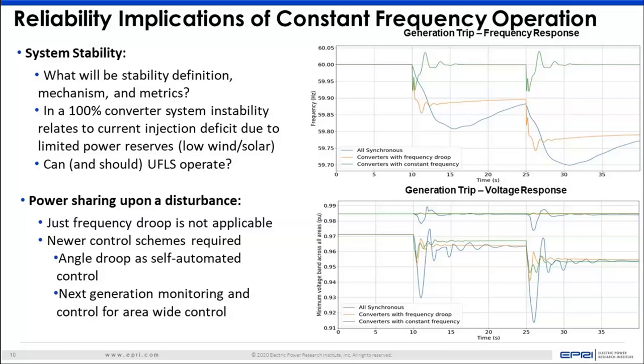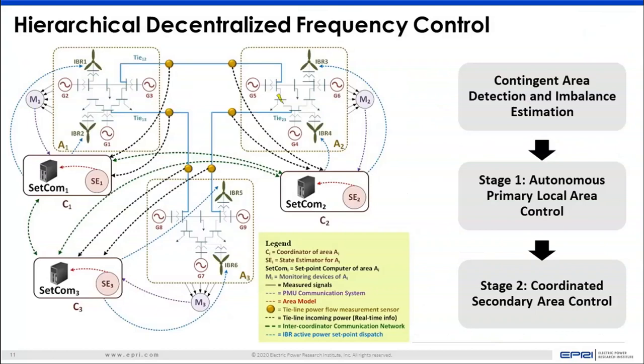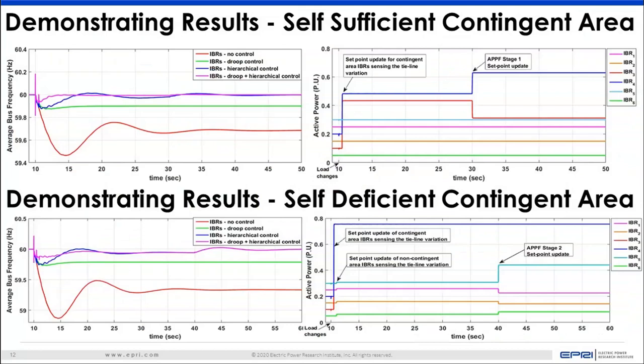So in addition to the distributed slack bus concept that we spoke about, we're also looking at it from the perspective of wide area control and next generation monitoring, where we have this entire hierarchical decentralized frequency control. We look at balancing areas or local areas within those balancing areas, and we make use of measurements and communication to quickly change the frequency set points and the active power set points of various resources in order to control frequency very tightly. As you see here with the purple curve, as compared to the red curve or the green curve, you can get much tighter frequency control by allowing these faster controls to play a role with very minimal incremental energy being supplied.